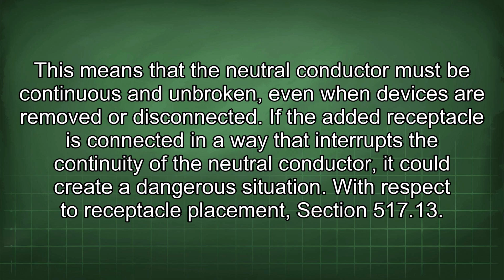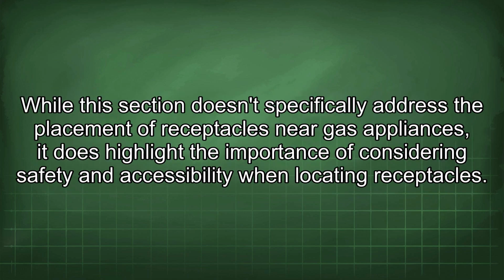With respect to receptacle placement, Section 517.13 of the NEC covers the location of receptacles in healthcare facilities, but it provides general guidance on receptacle placement. It requires that receptacles be readily accessible and located in a way that minimizes the risk of physical damage. While this section doesn't specifically address the placement of receptacles near gas appliances, it does highlight the importance of considering safety and accessibility when locating receptacles.